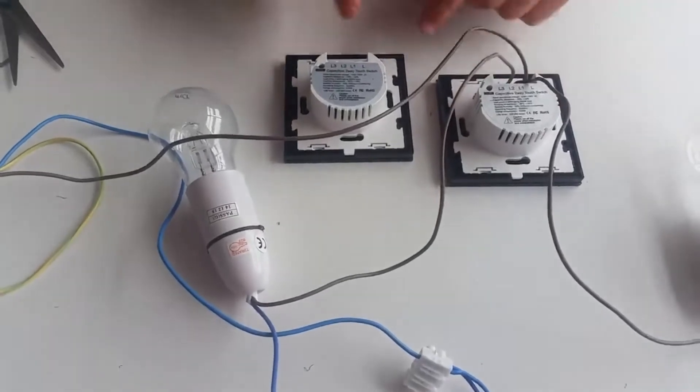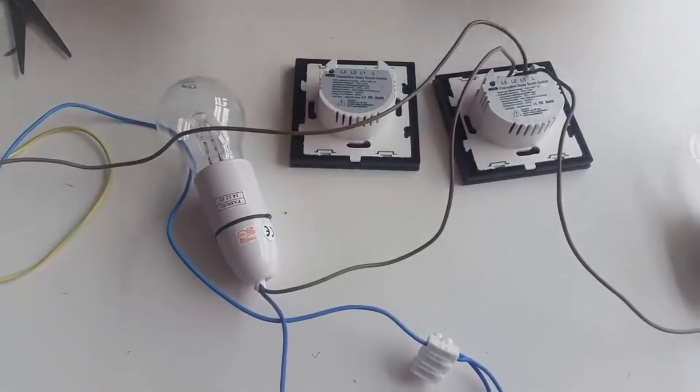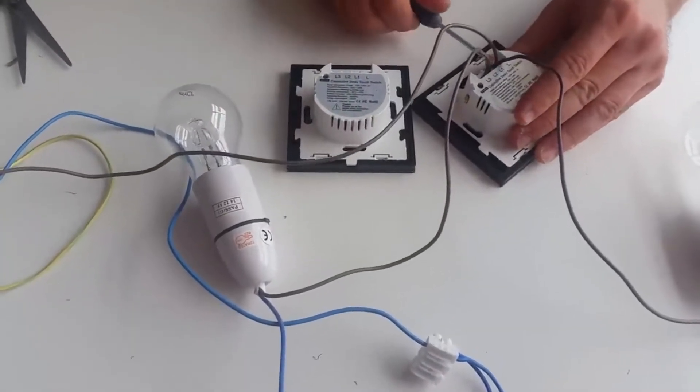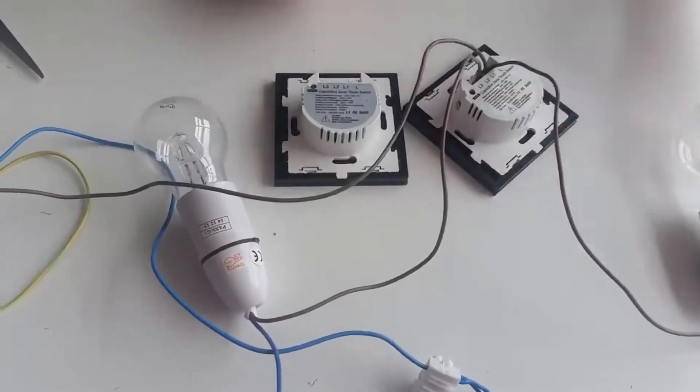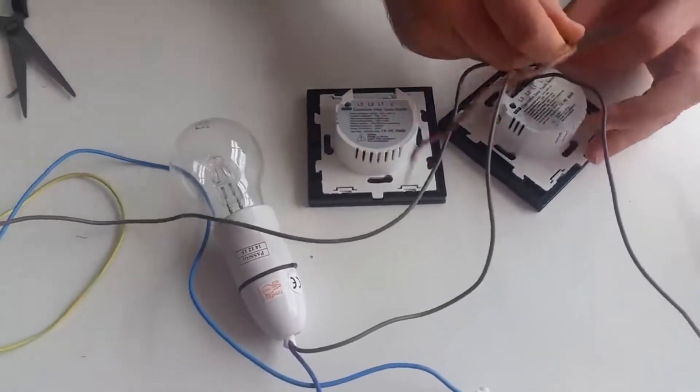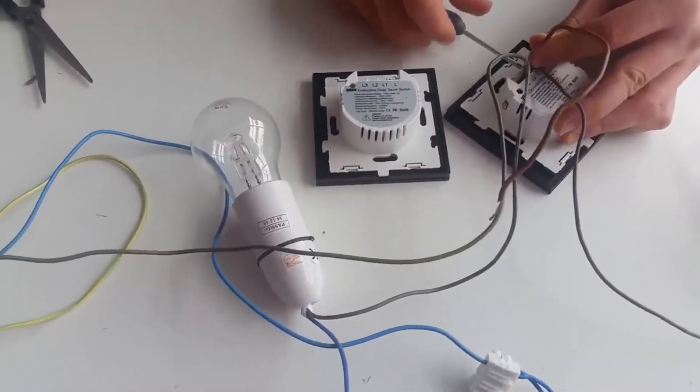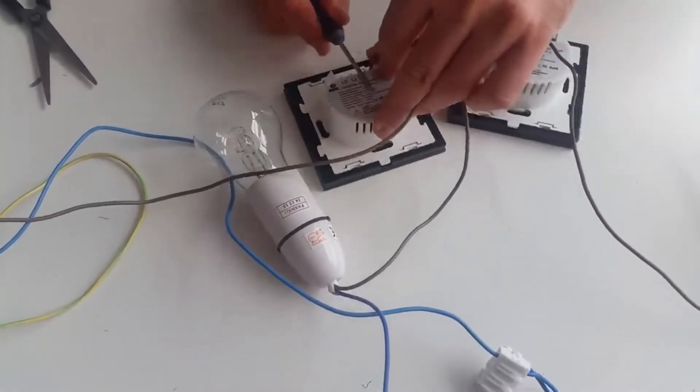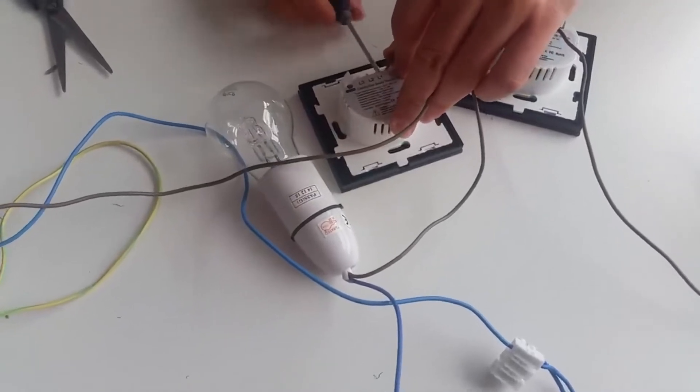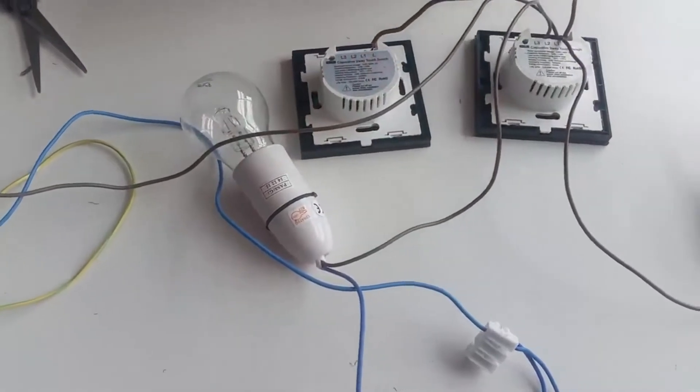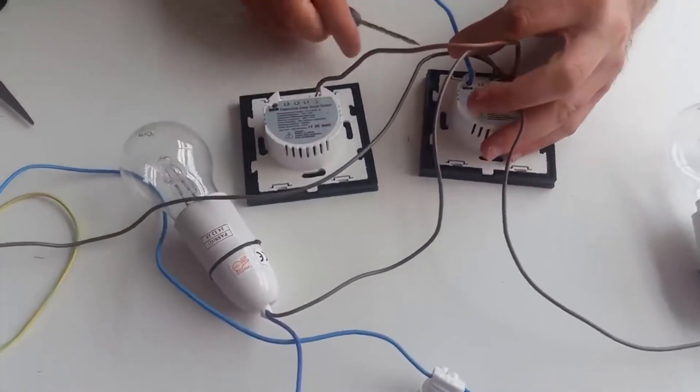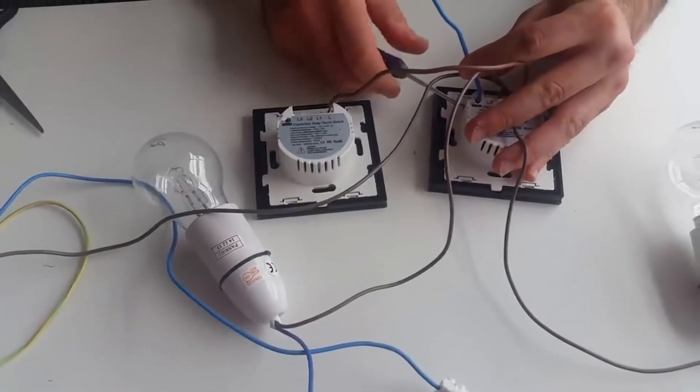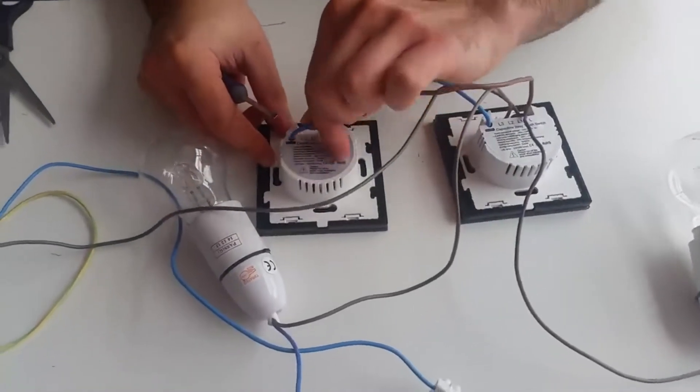To make these switches work as a two-way, you also need to have from your three core cable, connect one cable from the L terminal into the L terminal of the second switch. This will give power to the second switch. Then you also have another cable going from the two-way terminal of the first switch into the two-way terminal of the second switch.